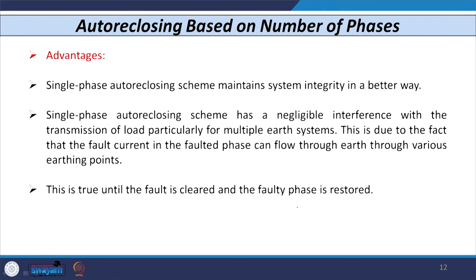The single phase auto reclosing scheme maintains system integrity better. It has negligible interference with the transmission of load, particularly when using a multiple earth system. This is due to the fact that fault current in the faulted phase can flow through the earth from various earthing points until the fault is cleared and the faulty phase is restored.